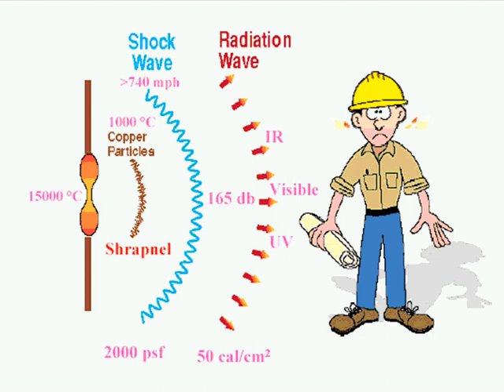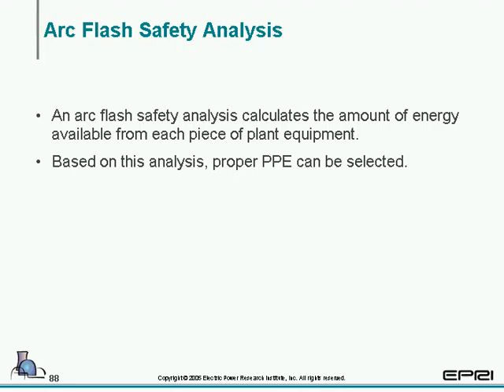Picture is worth 1,000 words, I always say. You have a shock wave, could be up to 2,000 PSF, a radiation wave, infrared, UV, up to 50 calories per square centimeter, in this case. It's got a 165 decibel there. That's the sound of the explosion. You have copper particles, shrapnel, any metal around the area. Once the explosion happens, might be coming your way. So it can be quite an explosion.